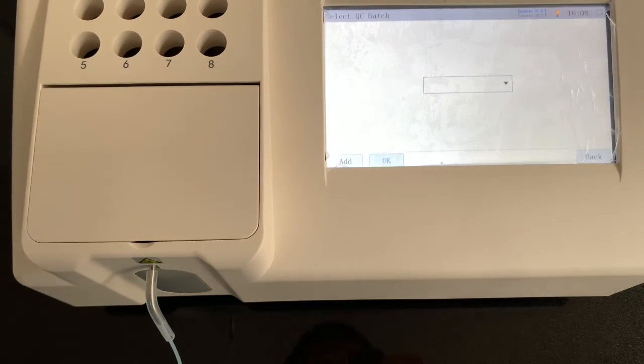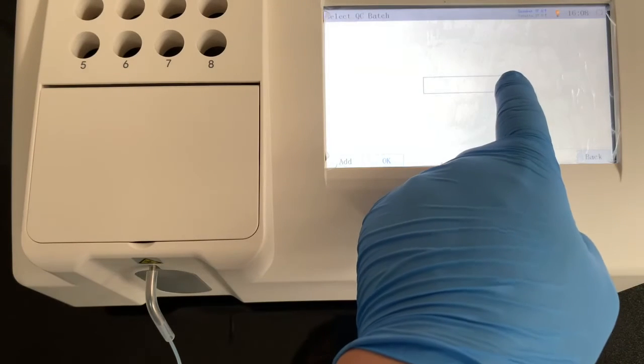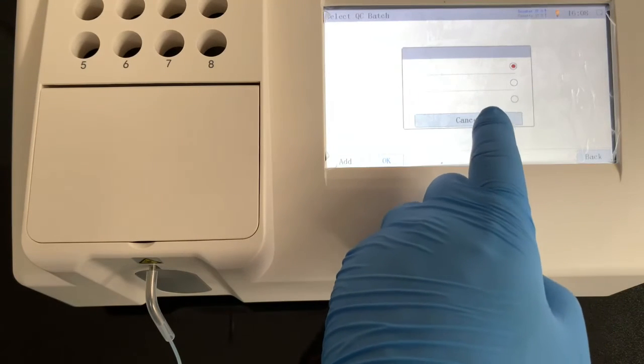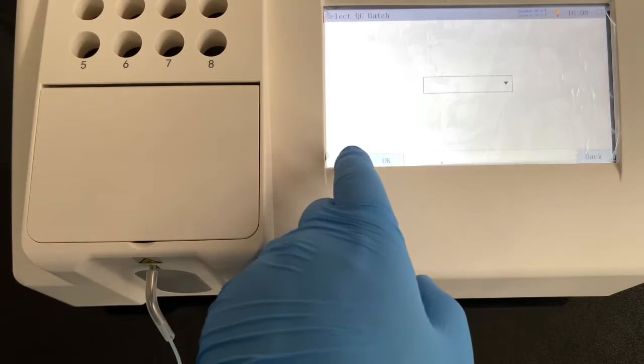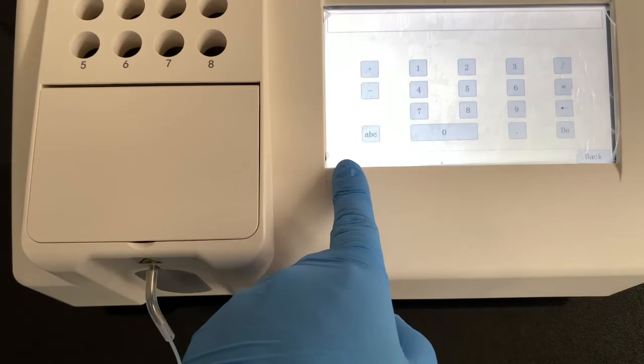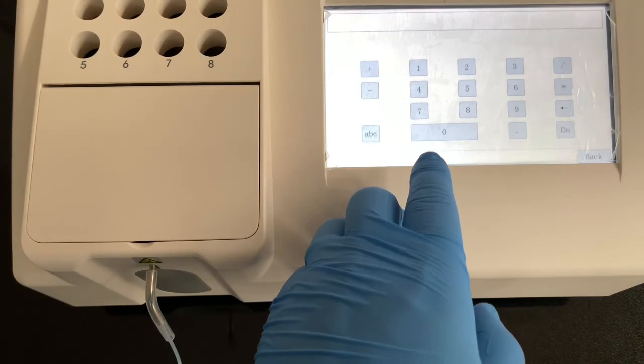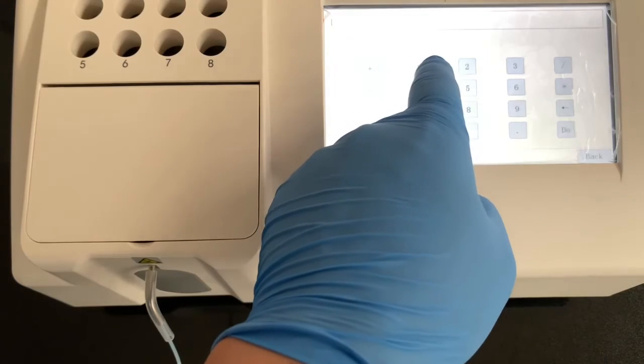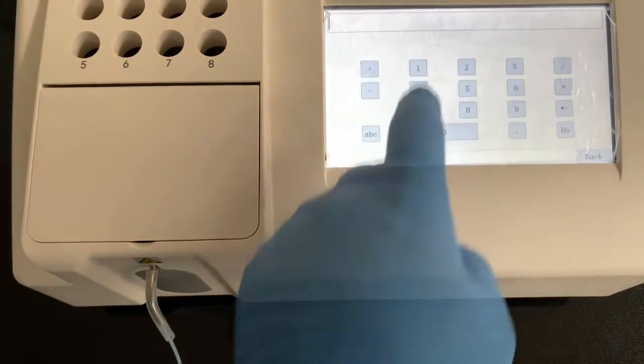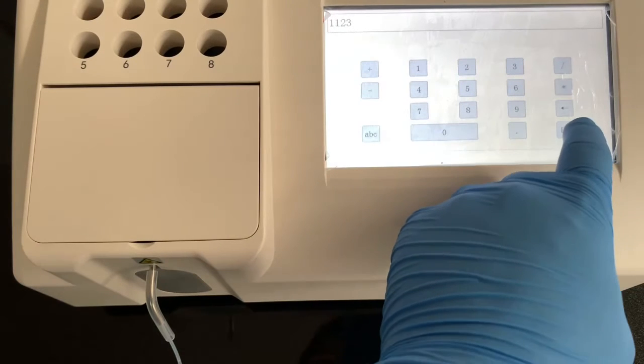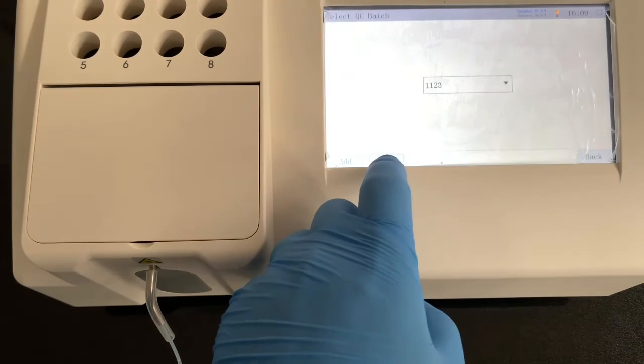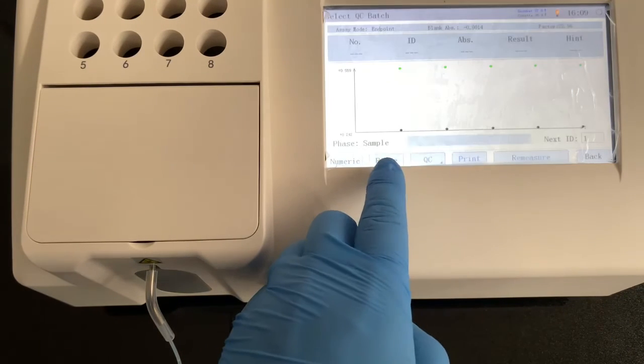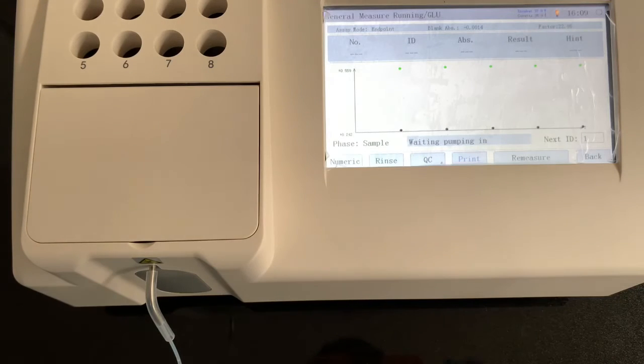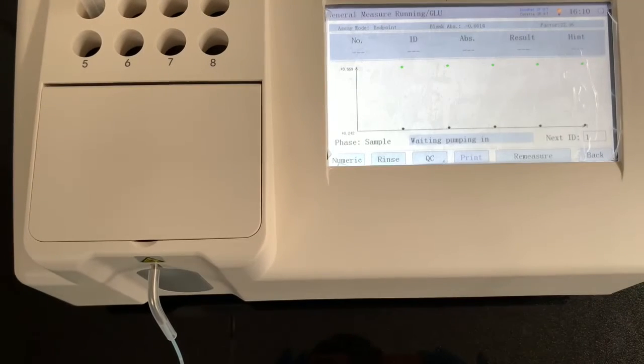After test QC, analyzer will request us to select QC batch. Here we click Add to input QC lot number. Click OK. Now the QC result is already saved in the database.